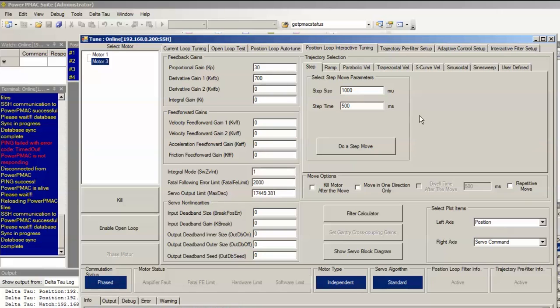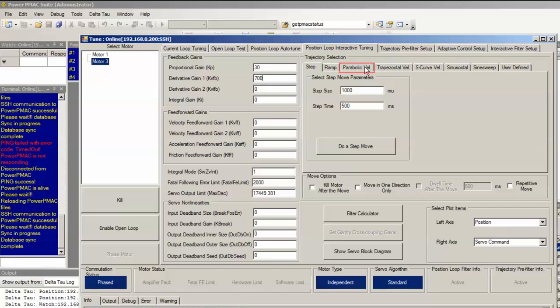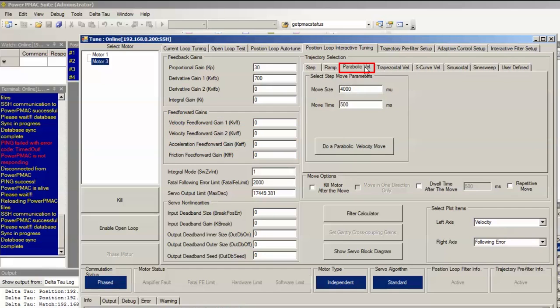So now that we've finished tuning Kp, Kvfb, and Ki, the proportional, derivative, and integral gains respectively with the step move, we want to move on to tuning velocity feedforward Kvff, acceleration feedforward Kaff, and friction feedforward Kfff. We do this through the parabolic velocity move. Select that tab.